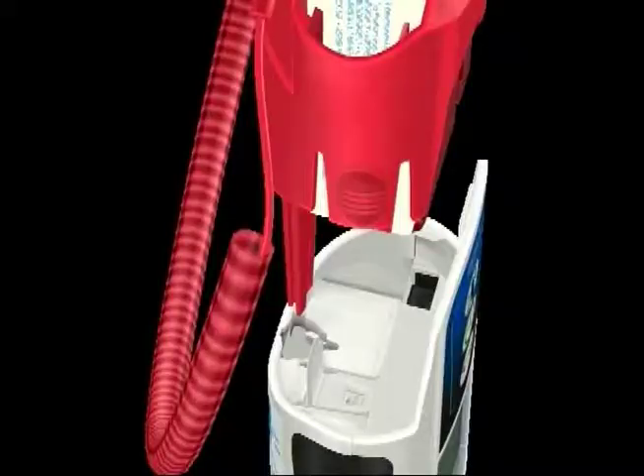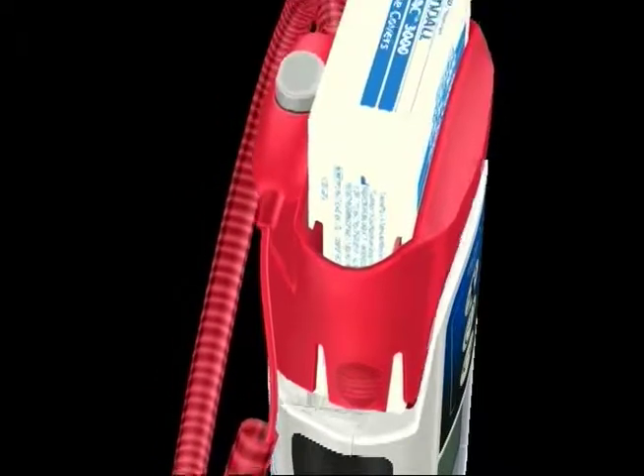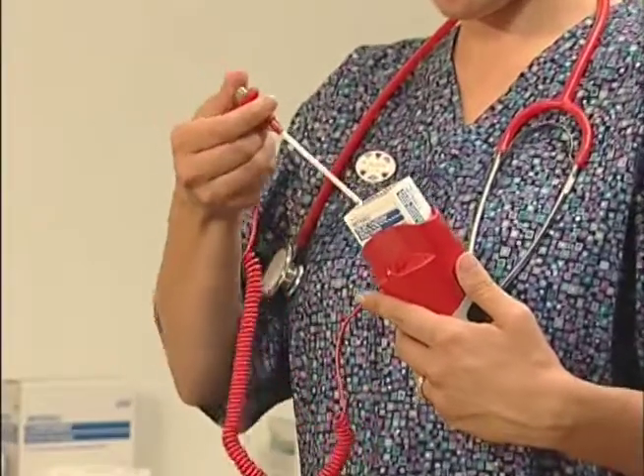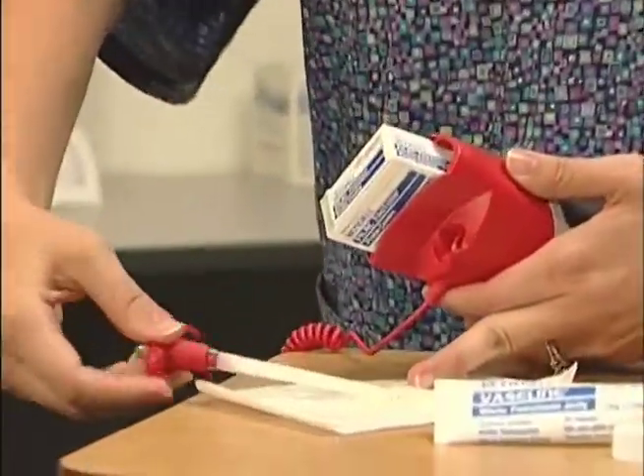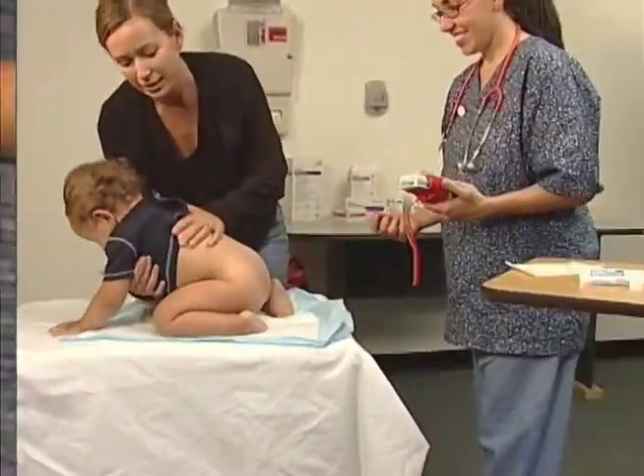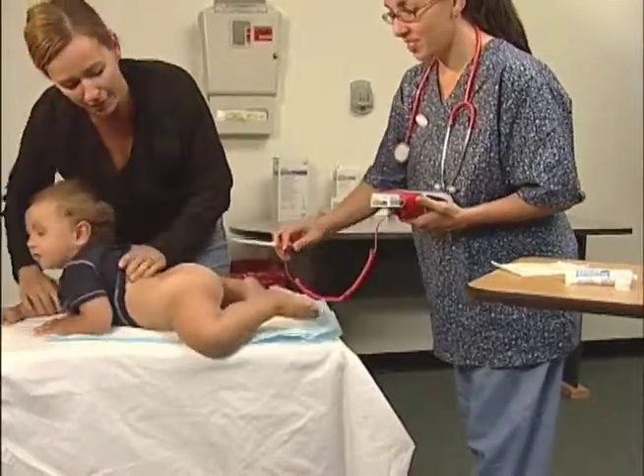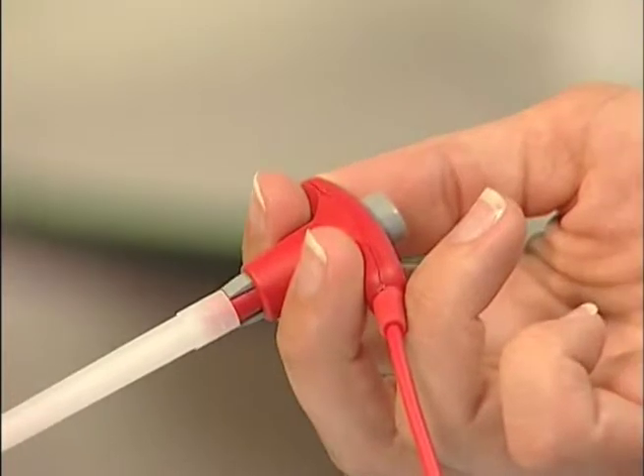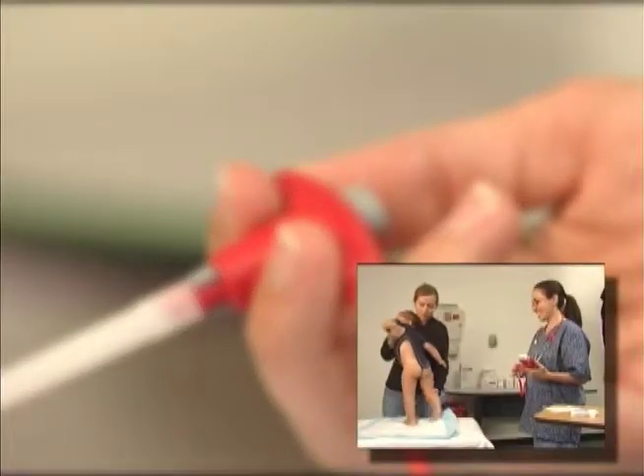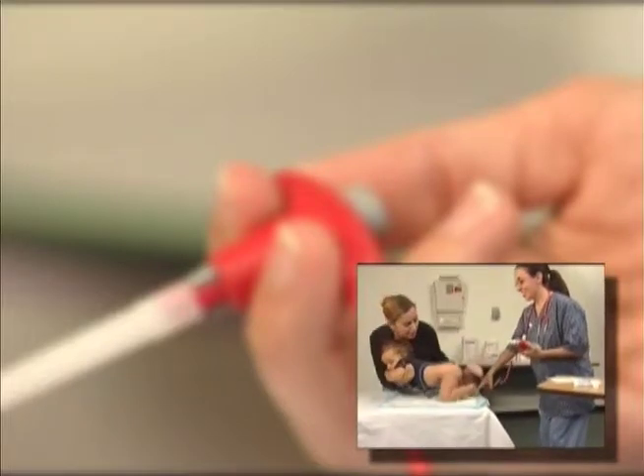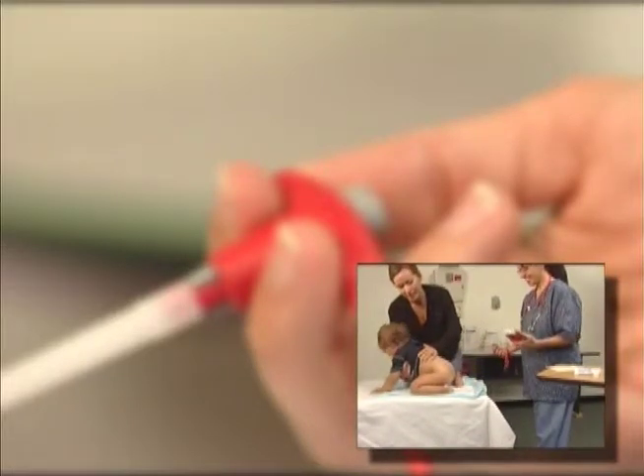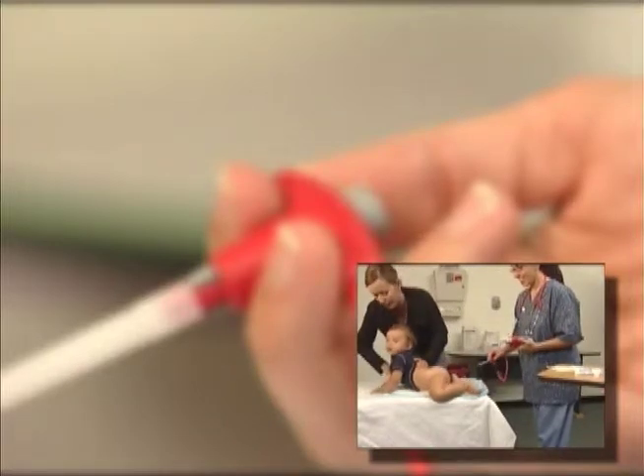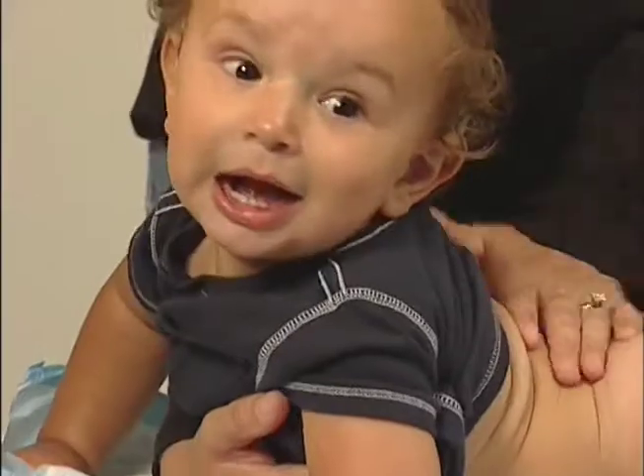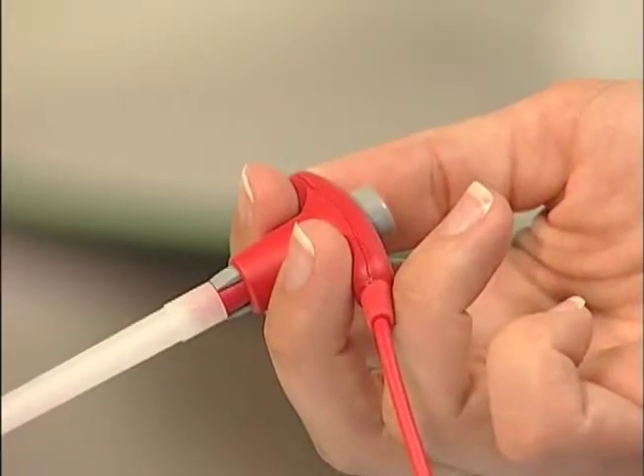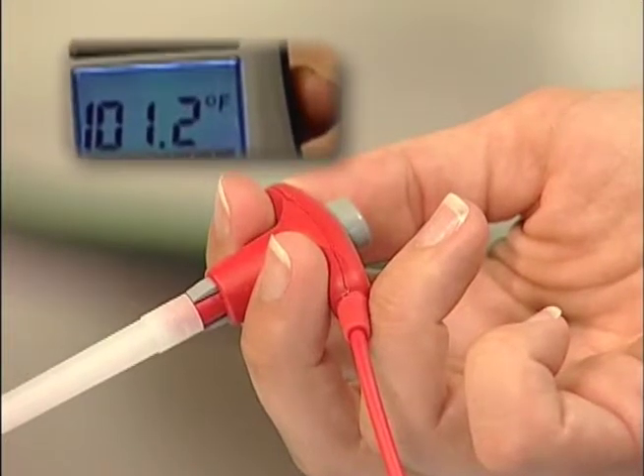When taking a rectal temperature, ensure the red isolation chamber and probe are properly attached and a probe cover has been applied. Apply lubricant to the probe tip if needed and insert the probe into the patient's rectum, angling it slightly to ensure good tissue contact. The depth of insertion for children is 1/4 inch to 1/2 inch or 6 millimeters to 13 millimeters. Insertion depth for adults is 1/2 inch to 3/4 inch or 12 millimeters to 19 millimeters. Have the patient remain as still as possible. Securely hold the probe handle until a long beep indicates that the temperature reading is complete and the final temperature is displayed.